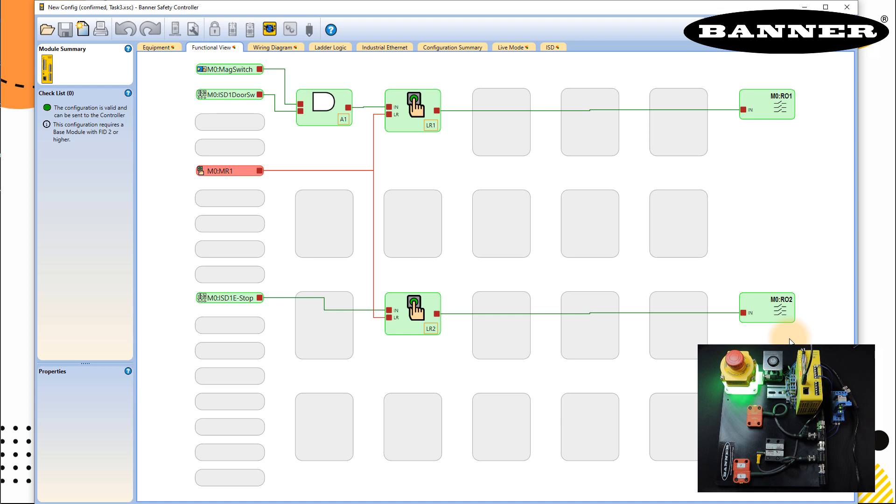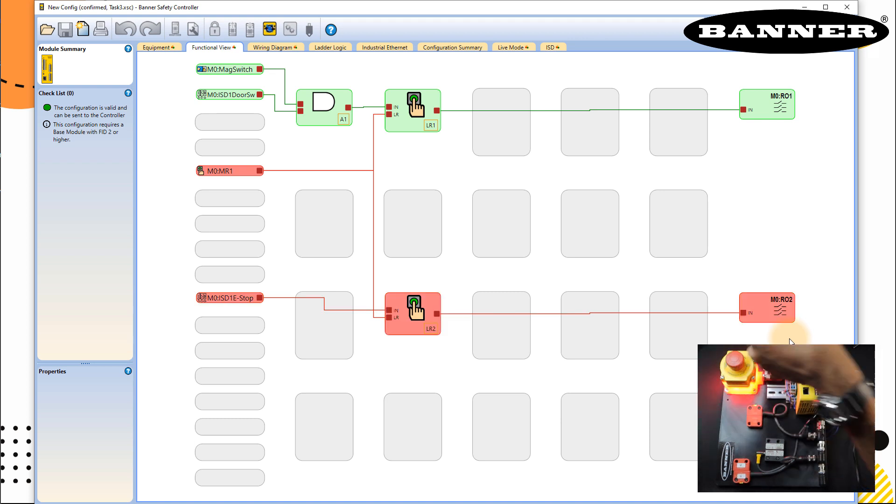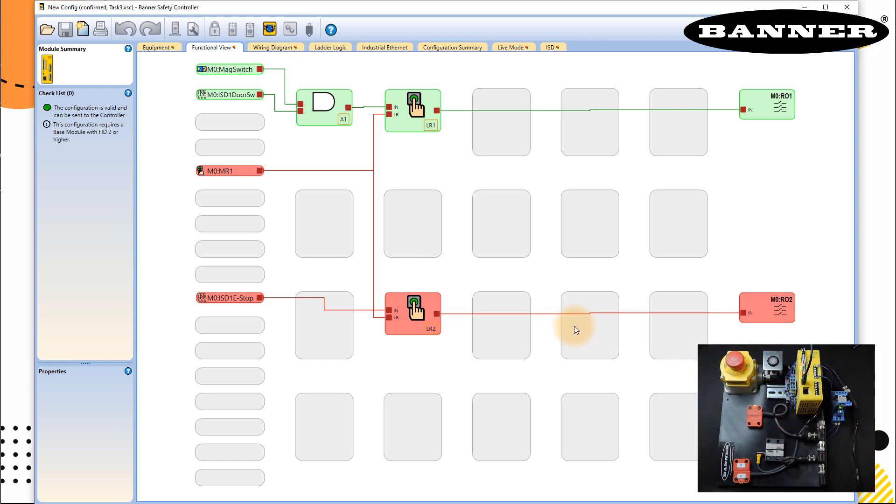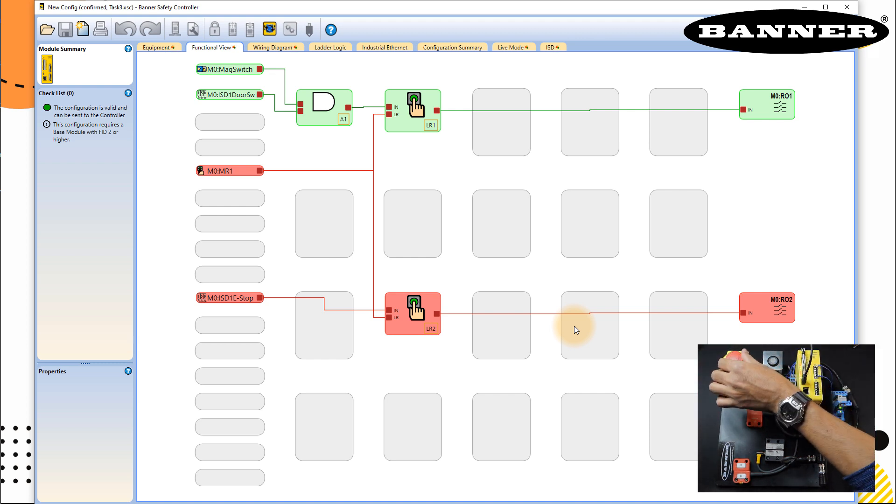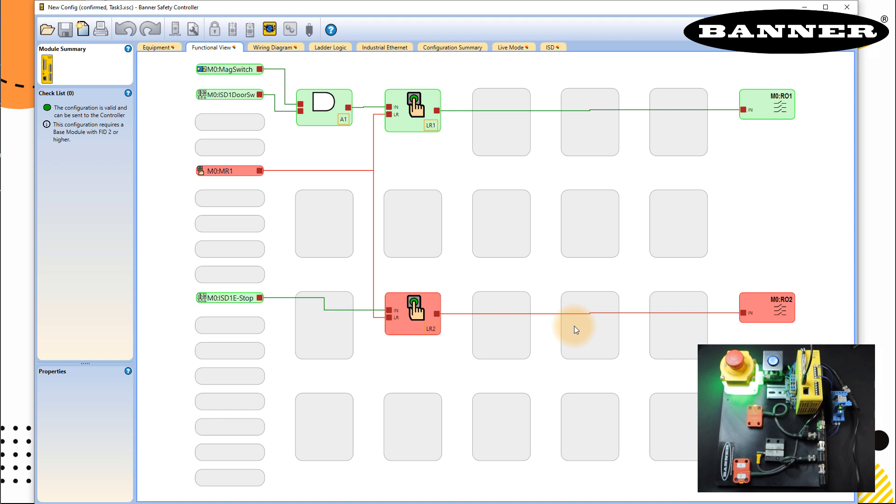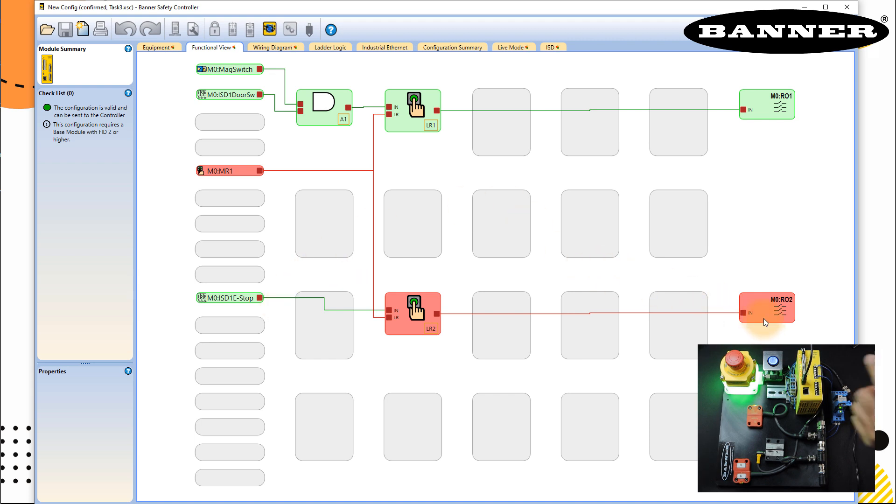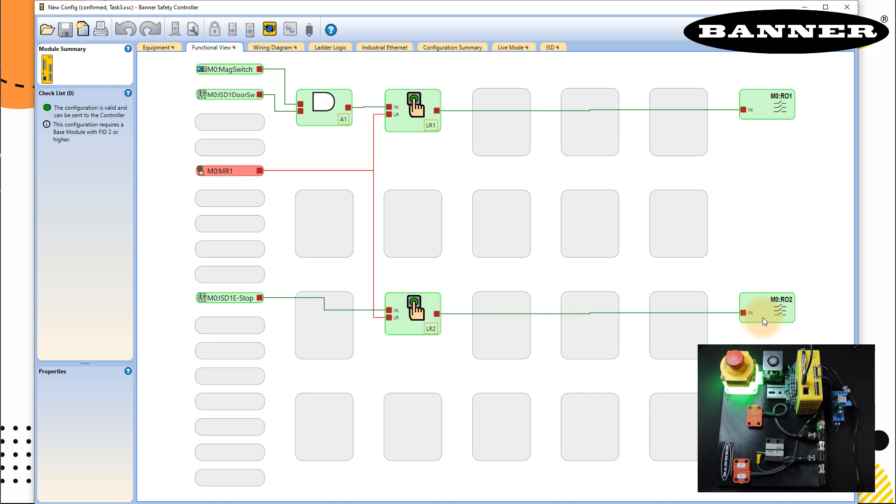Let's try with the E-stop now. We press the E-stop. And you can see that when the E-stop is pressed, you will not get the blue signal here, which means you have to solve your safety inputs, you have to solve the problems in your safety inputs. So you have to reset the button. And when all the safety inputs are true, then you get a blue light, which means now manual reset is required, enabled to actuate your RO2.